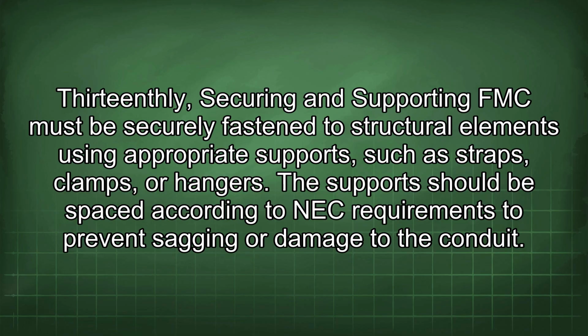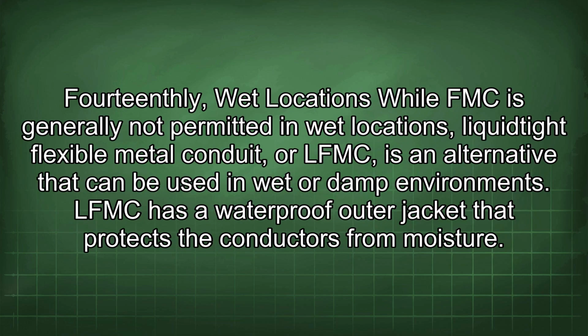13thly, securing and supporting. FMC must be securely fastened to structural elements using appropriate supports such as straps, clamps, or hangers. The support should be spaced according to NEC requirements to prevent sagging or damage to the conduit. 14thly, wet locations. While FMC is generally not permitted in wet locations, liquid-tight flexible metal conduit, or LFMC, is an alternative that can be used in wet or damp environments.